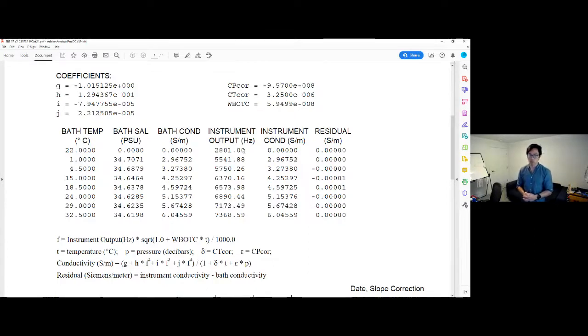For seawater applications, we recommend adding 500 hertz to this. So that would be what, 3,301 hertz. So when your 37 enters seawater, that's going to jump up by quite a bit more because it's salt water, higher conductivity. And then your pump is going to know, yep, I am safe to turn on. I'm not in air. I'm not going to burn myself out.